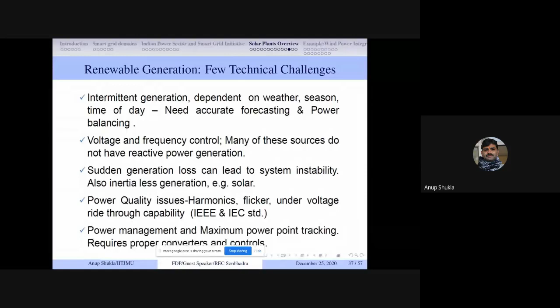Then there are power quality issues like harmonics—if power electronic devices are installed, some harmonics will be inserted into the grid, which we must manage according to IEEE and IEC standards. There's also power management and maximum power tracking, which require proper converters. I won't go into detail again on SCADA, EMS, thermal storage, and other microgrid challenges.